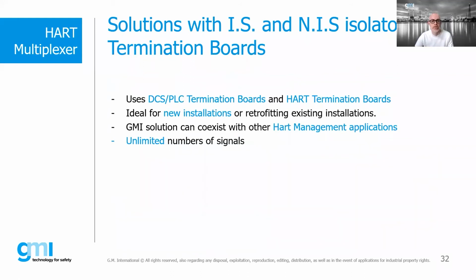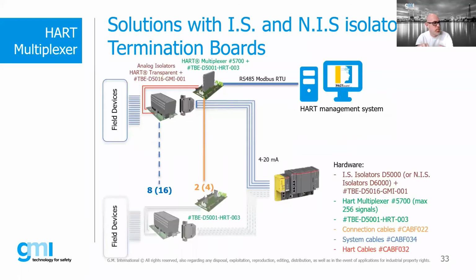Okay, thank you, Andre. The solution that involves the use of termination boards allows us to save considerably in terms of cabling. In fact, in the next slide, we will see the insert into the system termination board loop towards the PLC system. We will have the great advantage of being able to use a special cable that allows us to considerably reduce the connection to be made. With this type of connection, we will use a special termination board for the HART system, which in turn connects with the system termination board through flat cables that can manage up to 64 channels per board.